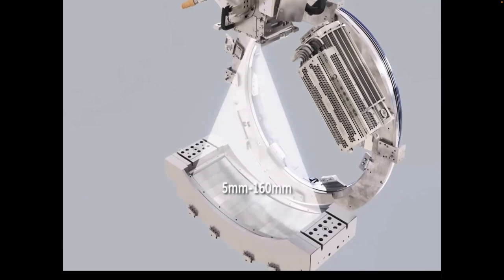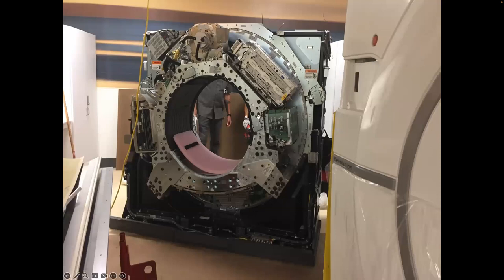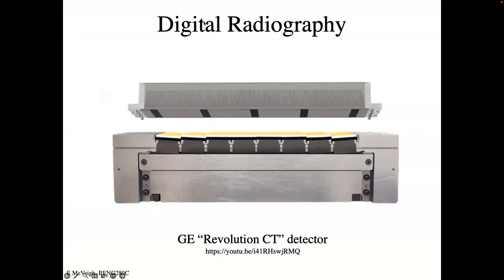A look inside the scanner during installation shows the x-ray tube, power supply, electronics, fans, and the detector array — all spinning at very high speed. It's recommended to search YouTube for 'spinning CT scanner' to see how fast these gantries rotate with the covers removed.